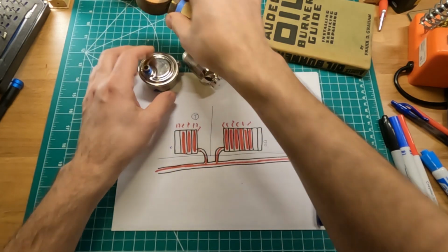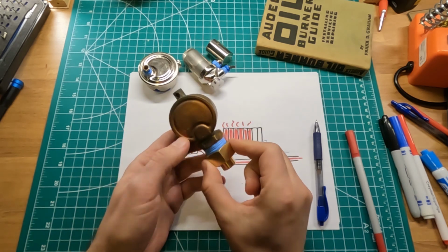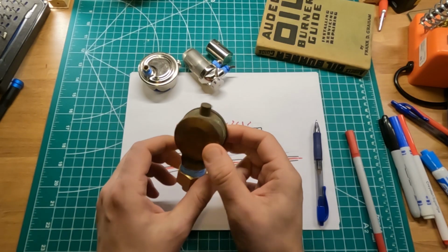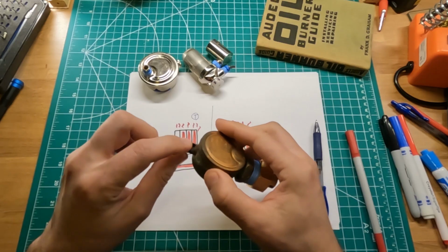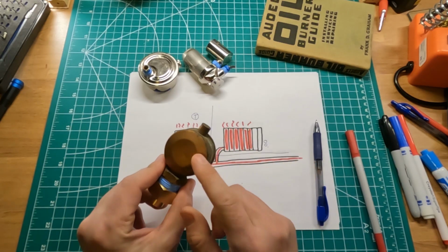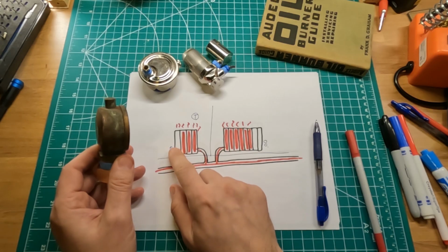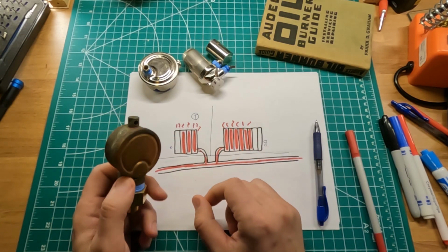How you cannot control it is that sometimes vents are like, let's say this one, this is a main vent, so obviously the large opening at the bottom shows you that this is a main vent, but this company Gorton also makes radiator vents that have preset openings, and you really can't control the venting rates, because the opening is always preset, continuously preset.